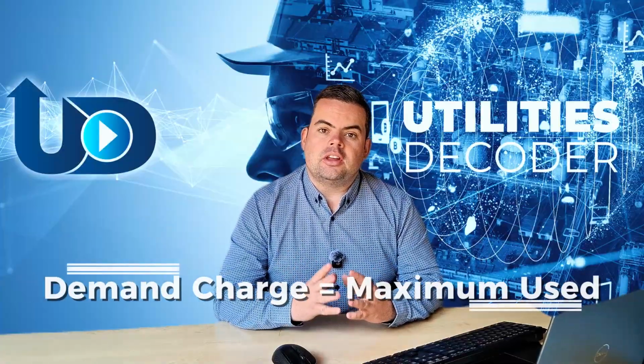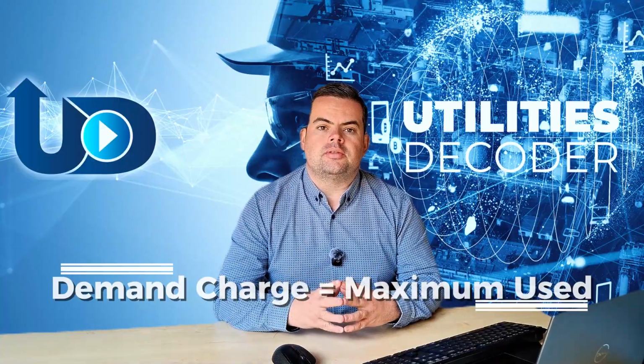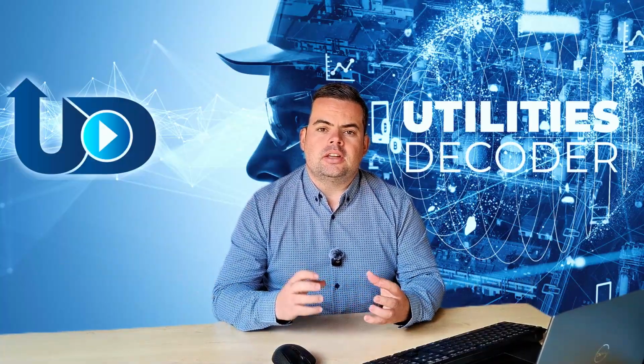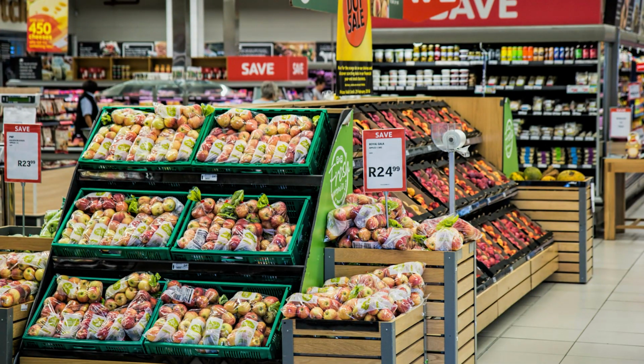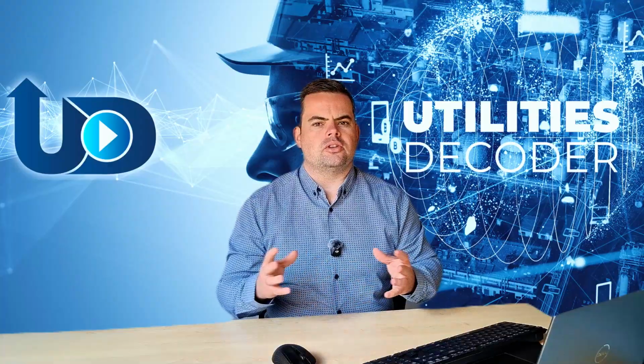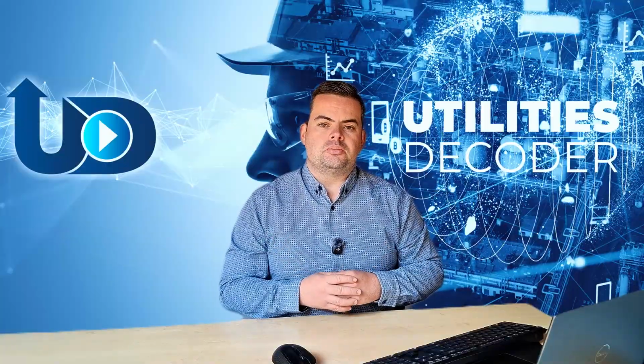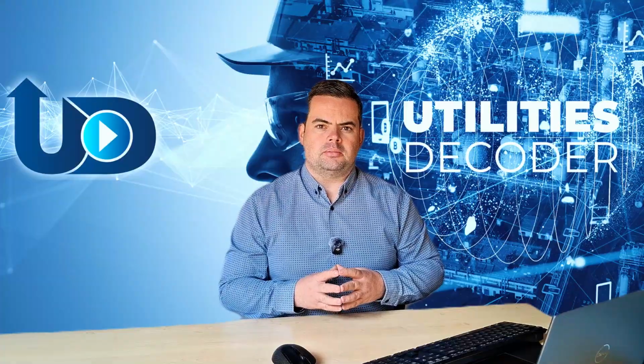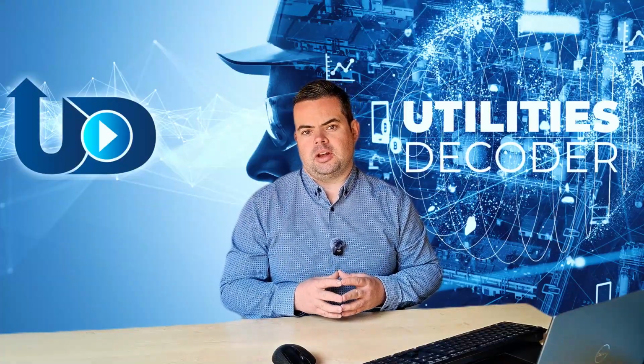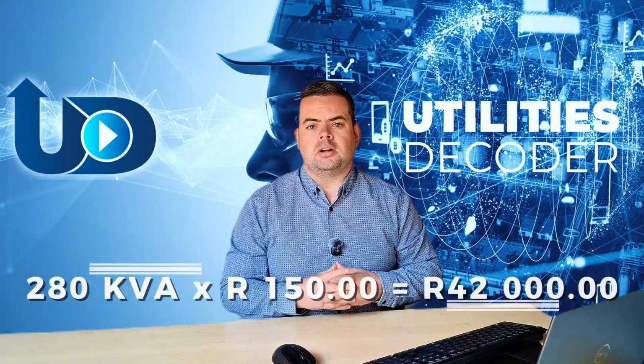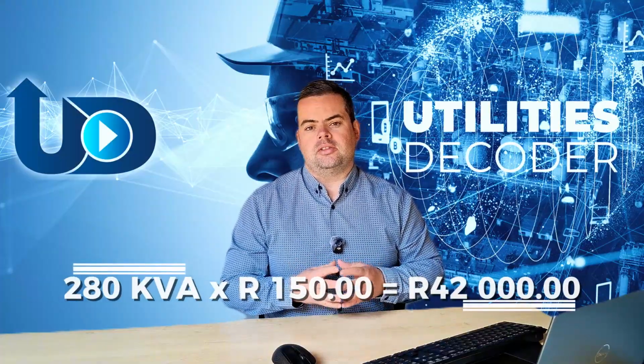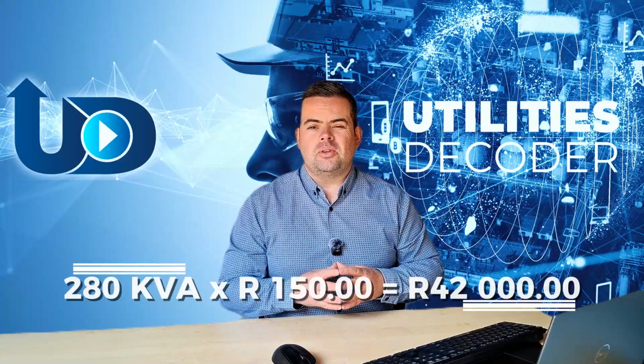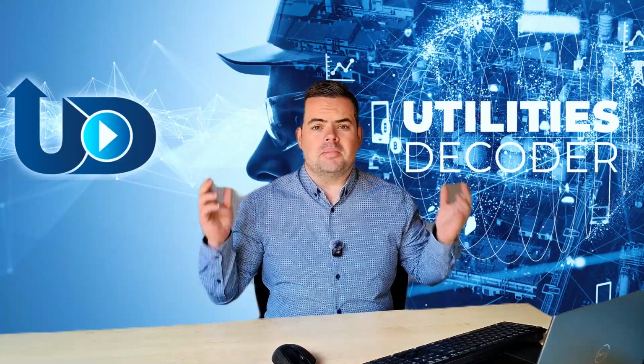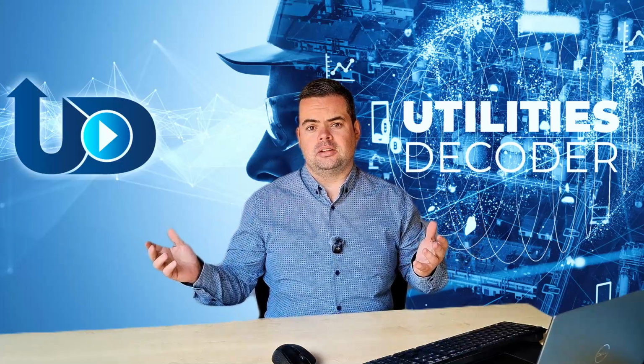Now demand charge, on the other hand, is the highest point of electricity that you use in a month. Now these peaks are normally measured in 30-minute intervals. If we were to take a practical example, such as the local spa in your neighborhood, these stores and establishments normally use an average of around 280 kVA in a month. If the store were to peak at 280 kVA for that month, and the rate was 150 rands per kVA, this would mean that we would need to multiply the 280 kVA by the 150 rands. It gives us a total of 42,000 rands for the month. Can you just imagine what some of these shopping malls and big centers are paying?